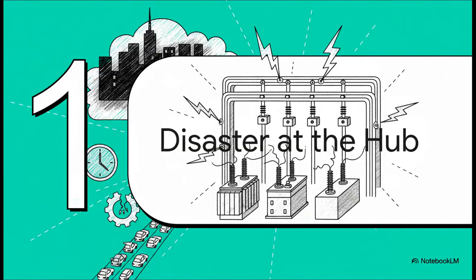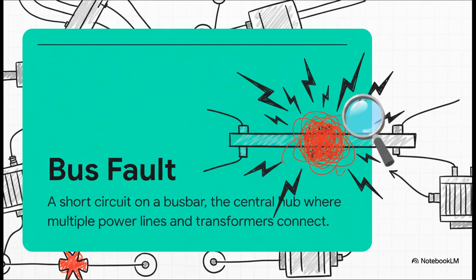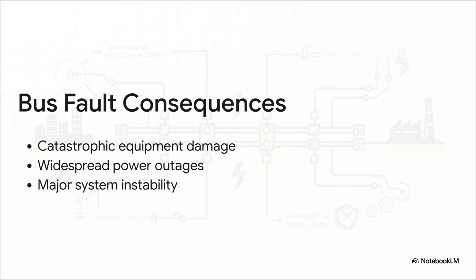But just like any major transportation hub, a disaster right there at the center can bring everything to a grinding halt. So what happens when something goes horribly wrong at this one critical intersection? Well, that disaster has a name. It's called a bus fault. This isn't just any old short circuit happening on a line miles away. No, this is a short circuit happening directly on the busbar itself. It's a failure right at the very heart of the substation, which is the absolute worst place for it to happen. And yeah, the consequences? They're huge. A bus fault unleashes so much energy it can cause catastrophic damage to equipment. It can trigger massive, widespread power outages because you've just taken out a key junction point. And it can throw the entire grid into chaos, causing major instability. So protecting this one piece of equipment is absolutely vital.